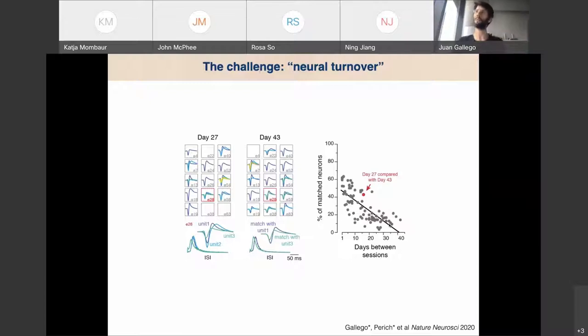This is probably a byproduct of the foreign body reaction in the brain, and can also be due to micro-movements of the electrode. What this means is that if you give a subject a very good BCI algorithm, it will work fine for a few days, but after a little while, when the neurons fed into that algorithm are completely different, the BCI will stop working. If we want to make a product that helps people at home for extended periods, we need to deal with this challenge of changing neurons.